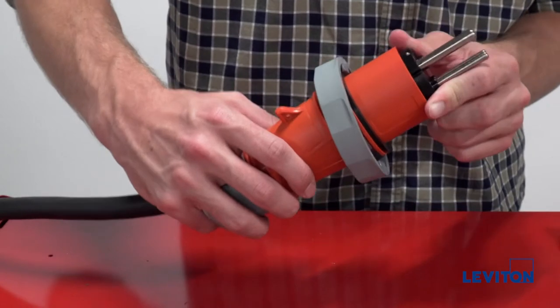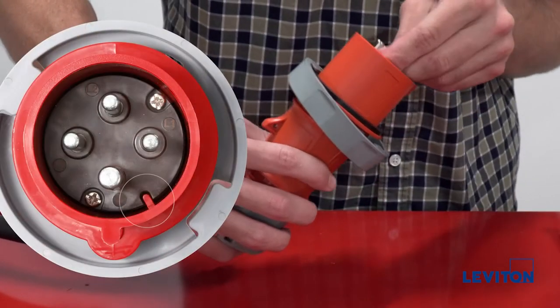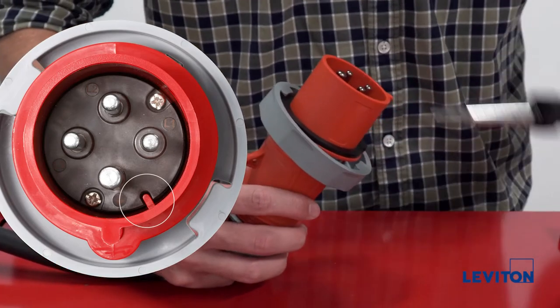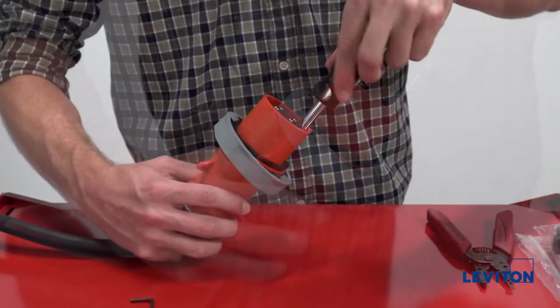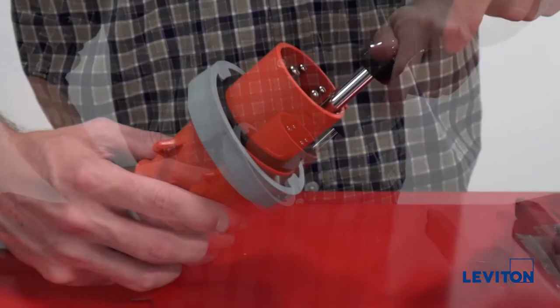Once the device has been wired, reconnect the contact carrier to the housing. Be sure to line up the key on the contact carrier with the notch inside the housing. Next, tighten the assembly screws with the screwdriver to 8 inch pounds.